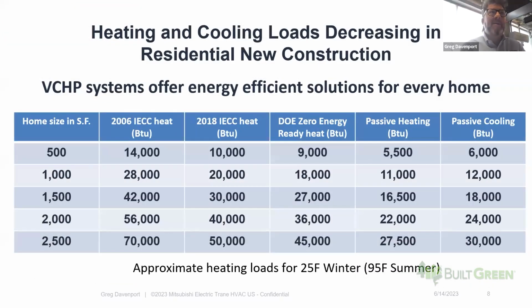Just like we saw the HERS score coming down lower and lower as homes were built under newer, more energy efficient codes, the same correlation is true for heating and cooling. Homes used to average, in HVAC slang, a 'ton' — 1 ton equals 12,000 BTU of heating or cooling. 20 or 30 years ago, every house was a 4 or 5 ton house. We've come a long way building better envelopes and more energy efficient homes, and most homes in Washington State now are under 3 tons.